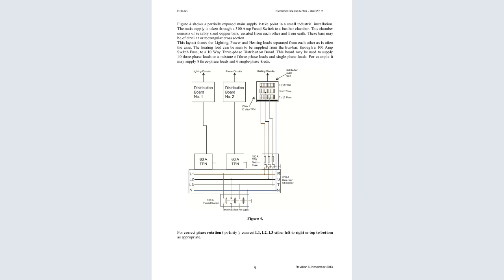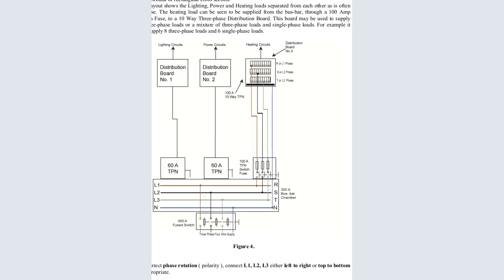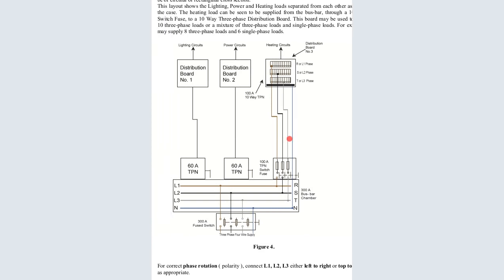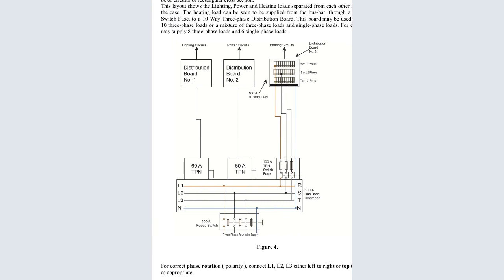So this board may be used to supply 10 three-phase loads or a mixture of three-phase loads and single-phase loads. For example, it may supply 8 three-phase loads and 6 single-phase loads. So you can see it here. This is a distribution board. This is a distribution board again. This is now the three phases, the way they are supplied. So this is now the switch. This one is from the main, that is the three-phase four-wire supply.